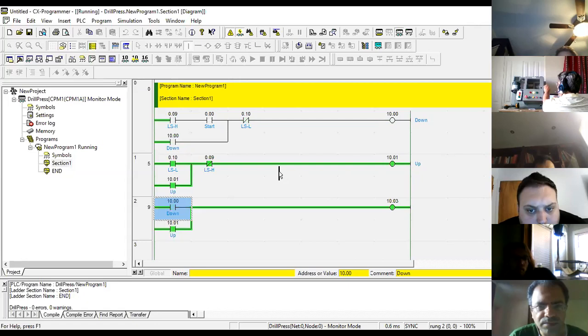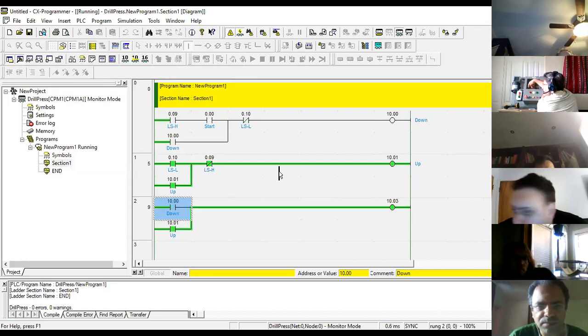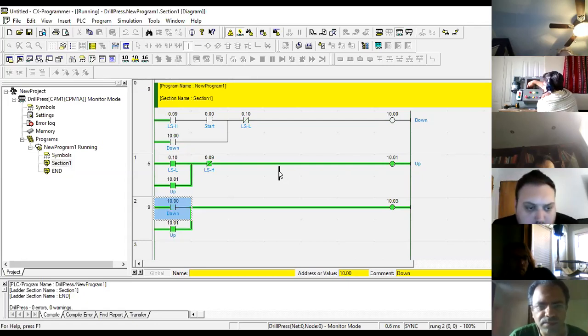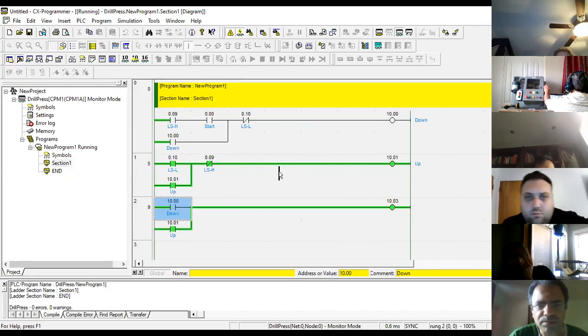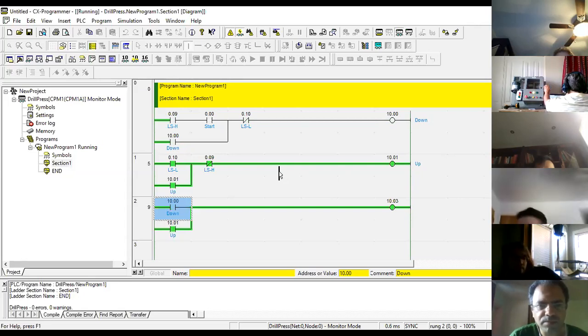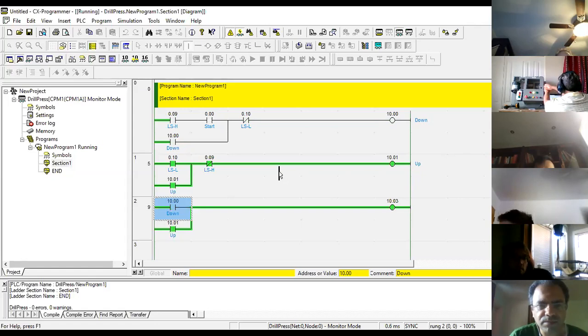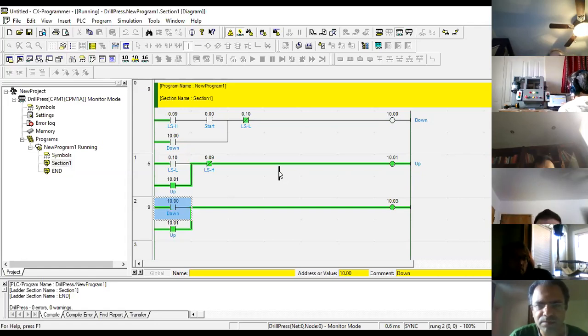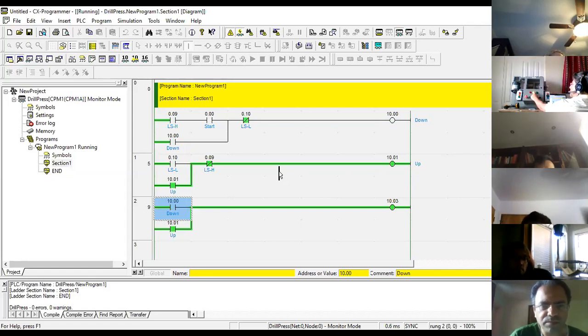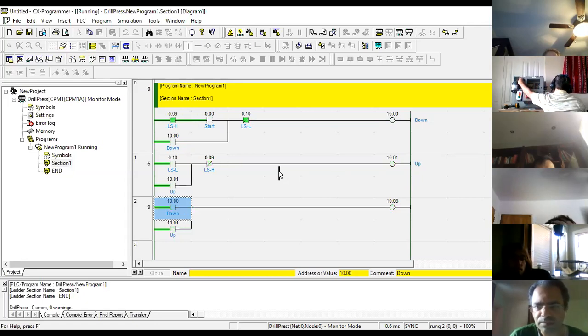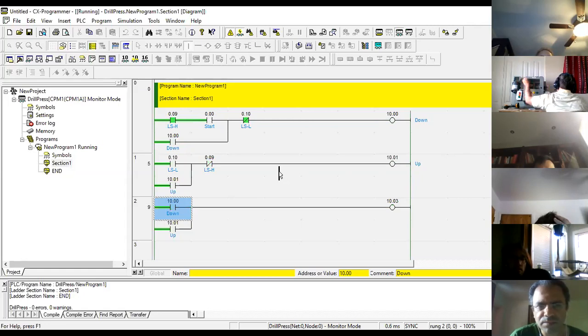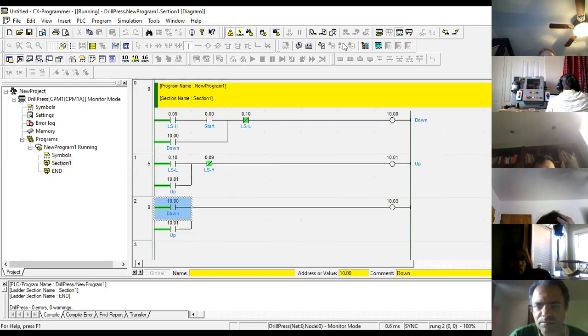Okay. I don't know if you heard that, but the contactor is transferred. It was my down, now it's going up, but as it's going up, I'm going to let go of this limit switch. It has to continue to go up. And as it continues to go up, the drill is still turning until it hits the upper limit switch, which turns everything off. So that's the actual program. That's the whole thing.